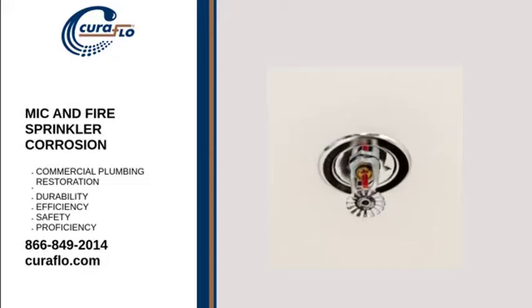Defined in the Fire Protection Handbook, MIC, or microbiologically influenced corrosion, is a type of corrosion where the electrochemical corrosion interaction is accelerated and concentrated by specific bacteria being active within a fire sprinkler system. This results in the metallic system components failing prematurely. MIC does not only exist in the fire protection industry.